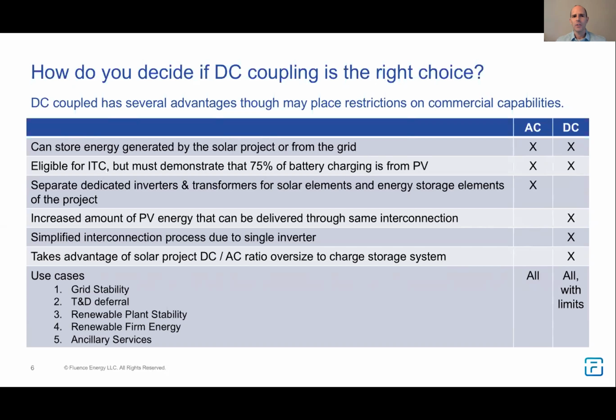The next topic is something unique to the United States, the eligibility for the investment tax credit. Both AC and DC systems can be eligible for this ITC. There's a bit of a misnomer that it must be DC coupled in order to capture this, but it can be either AC or DC coupled, though in either case you need to demonstrate that at least 75% of the battery charging is coming from the PV source and not from the grid.